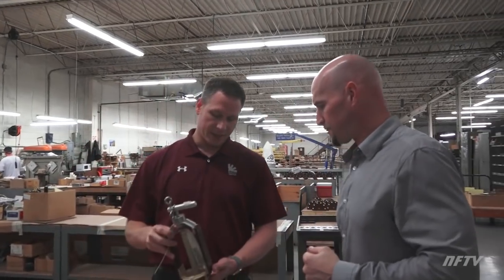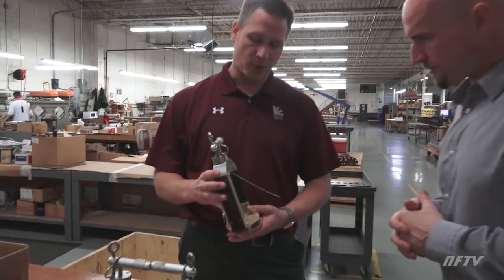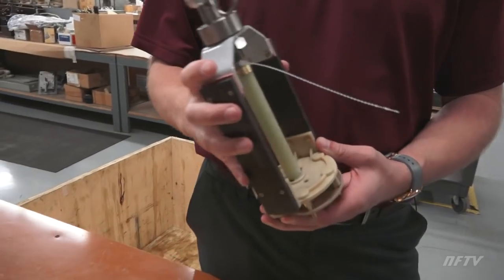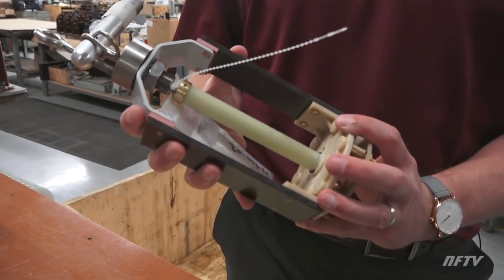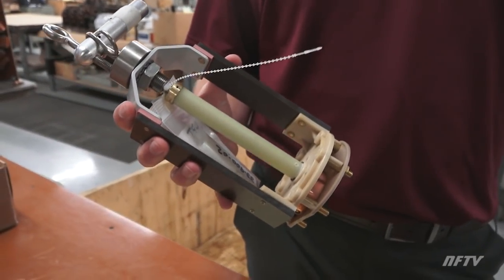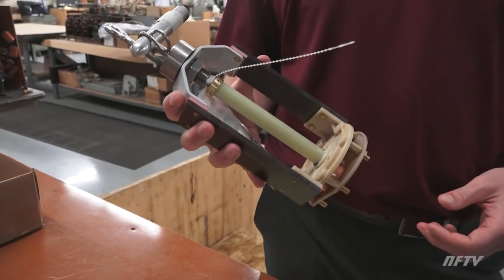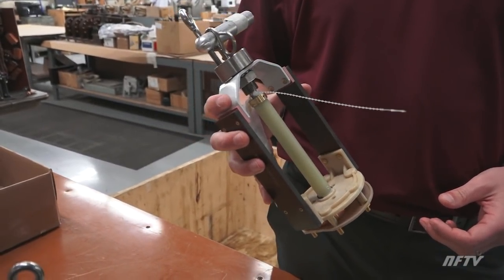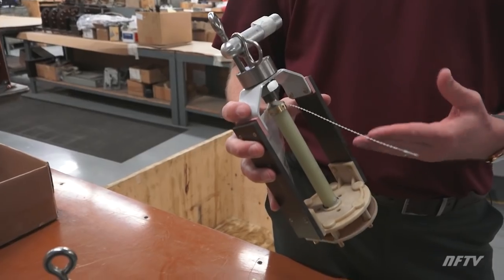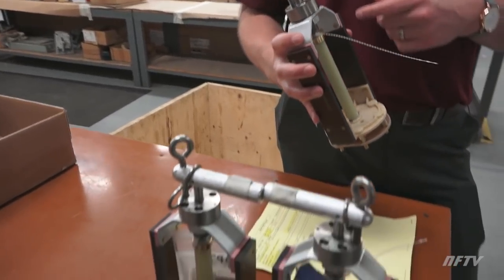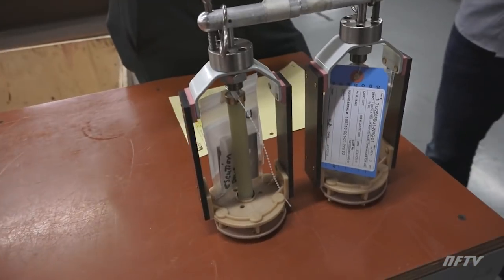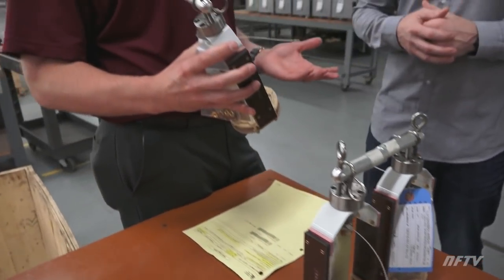This particular design is used in a pole top type transformer. It's a single phase unit, so it's only got one switch deck, unlike others we looked at that had three decks for three phases. We would typically sell this component to a transformer manufacturer, who would install it and connect all of their tap leads up to it. Again, it's just used for voltage regulation.